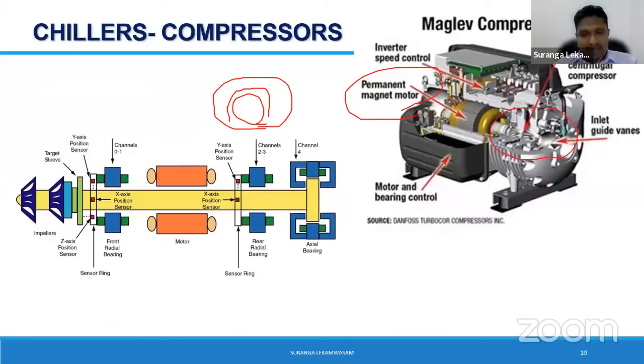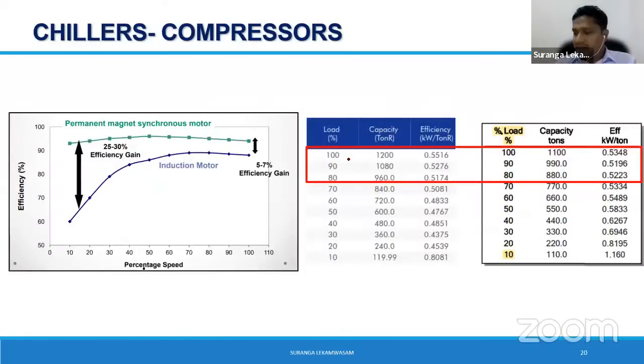The other beauty is that whatever capacity range you need for your magnetic bearing chiller, whether it is 100 to 1,000, you will have only centrifugal compressors, because with this high RPM you can't rely on positive displacement machines. Therefore, the compressor is a centrifugal compressor here. Then a lot of advanced electronic features are incorporated, which obviously improve the efficiency. This is not a new technology, I would say. It has been in the industry for the last 10 years. It is a good machine as long as you select wisely. I have seen people think it is good in efficiency, but if you install blindly, you can't get the expected savings.